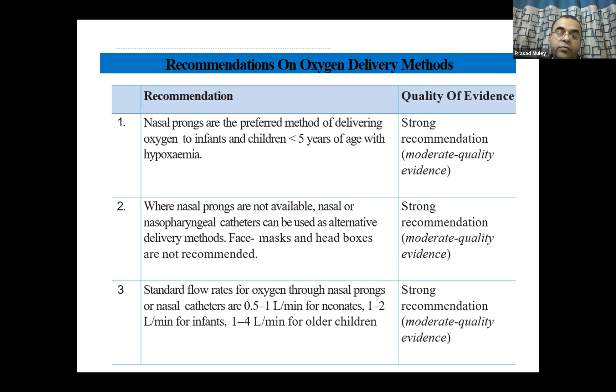The maximal flow rate for nasal cannula is 0.5 to 4 liters per minute. Simple face mask is 6 to 10 liters per minute. Partial rebreathing is 10 to 12. Non-rebreathing, which we commonly know as NRBM, is 10 to 12 or 10 to 15 liters per minute. Oxygen hood is 10 to 15 liters per minute, and Venturi mask is variable.